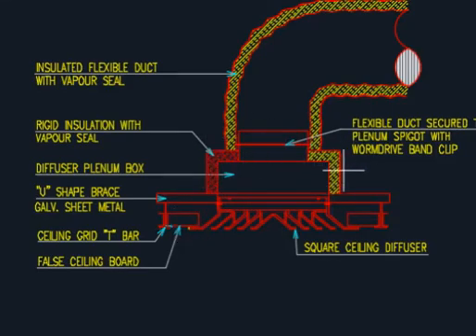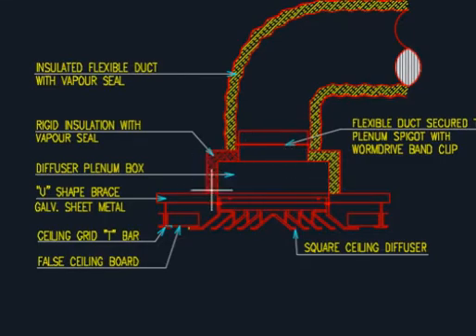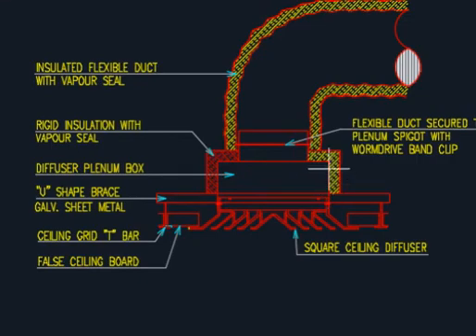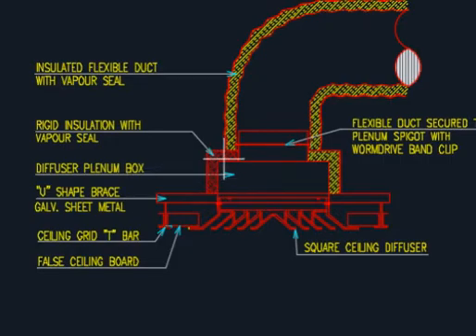This is a plenum box. What is a plenum box? We have already explained it several times, but now we will explain it for those who are new and watching for the first time. So basically, whenever you have to connect to the diffuser, before the diffuser there will be a plenum box. Inside the plenum box, there is an acoustic lining. So if air is coming through, it can create sound — the plenum box will eliminate that sound because it has cloth-like material with small holes. So we call this acoustic lining ducts.